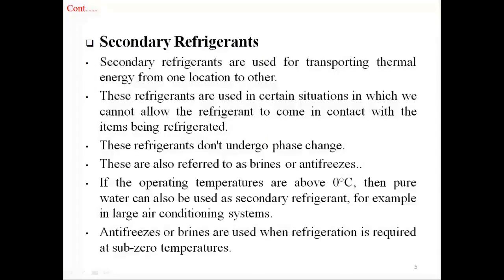Secondary refrigerants are used for transporting thermal energy from one location to another. These are used in situations where we cannot allow the refrigerant to come in contact with the items being refrigerated. These refrigerants do not undergo phase change, whereas primary refrigerants undergo phase change from liquid to gas and gas to liquid. They are also referred to as brines or anti-freeze. If operating temperatures are above zero degrees Celsius, pure water can also be used as a secondary refrigerant, for example in large air conditioning systems. Anti-freeze or brines are used when refrigeration is required at subzero temperatures.